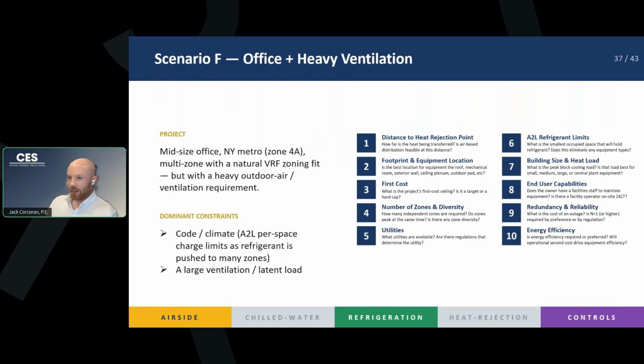And our last scenario here is a mid-size office, right? Many projects that we do here in Manhattan are office type buildings. We're in New York State climate, New York City zone 4A. There's many zones. And it makes sense for a VRF fitting, right? We don't have any central equipment rooms, but we do have heavy outdoor air loads and a ventilation requirement. There's maybe a swimming pool that has a high humidity. Maybe there's a space with lots of people in it, which drives our outside air ventilation rates up.